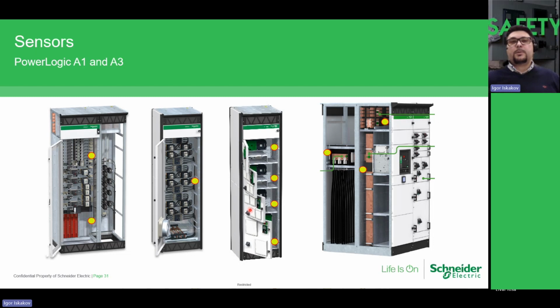And especially we have units with 12 sensors. You can cover a huge switchgear part with only 1 unit. And if you remember, it has the power supply and the LED, so it has everything you need. Also the fast tripping contact, less than 2 millisecond tripping on your circuit breaker, will provide the best arc flash protection which is actually available on the market.